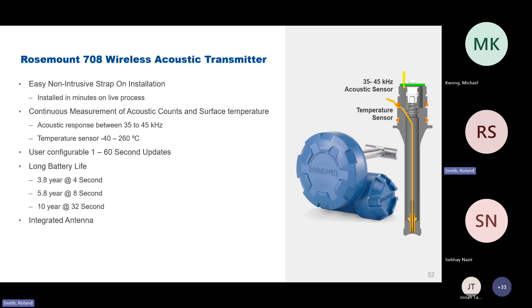So some of the applications that we get into on these are steam trap monitoring or PRV liftoff. You can well imagine if we have a PRV on a steam vessel, and we have a liftoff, obviously, it's going to make a lot of noise when that relief valve lets go, as well as there will obviously be a big temperature shift when steam gets vented through that piping system downstream. So that temperature and acoustic are combined to be able to advise customers when and how long their PRV has been opened up, and even more importantly, in a lot of cases, when it reseats. Very common issue with safety and relief valves is chatter. They'll sit there and not fully reseat. So this is another way that the 708 can help operations not waste steam or any other process gases, for example.